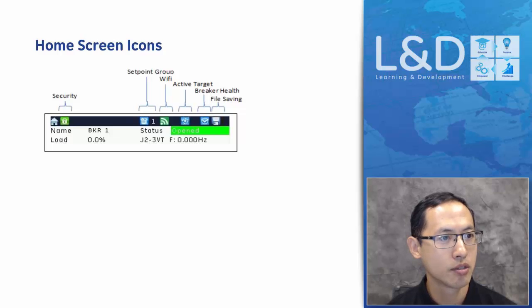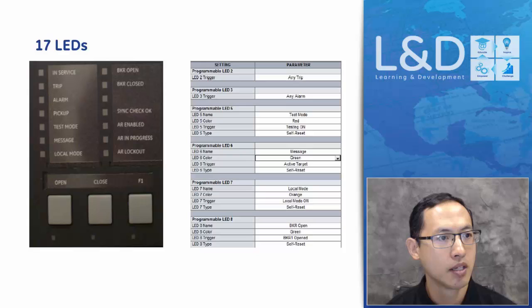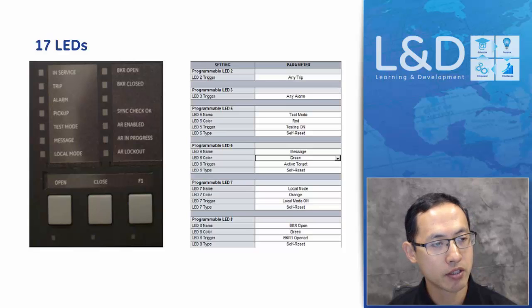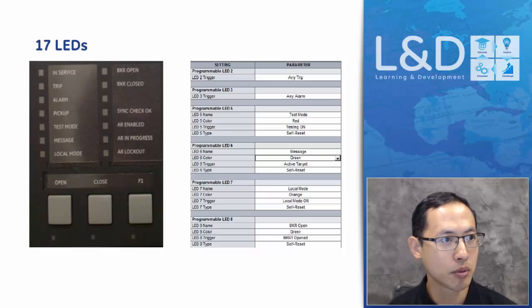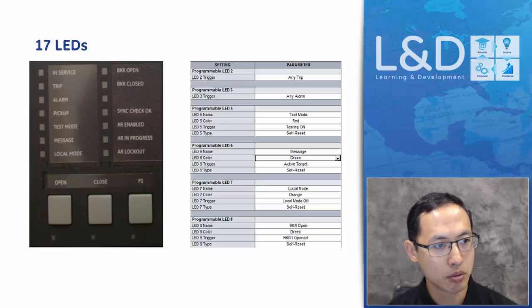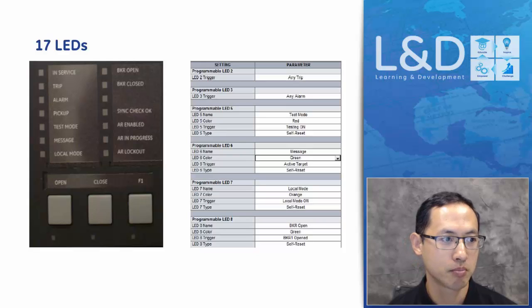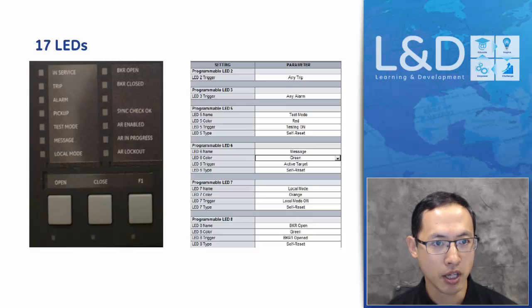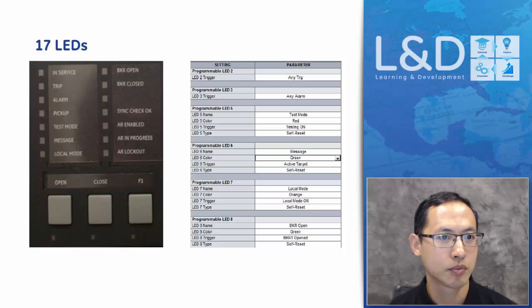We can also see the circuit breaker status, open or closed, and we can see the load current and the measured VT frequency. So for the programmable LEDs, there are 14 LEDs on the top. 2 of them are not programmable, that's in service and pickup. So there are 12 programmable on the top and 3 programmable at the bottom, so totally 15 programmable LEDs. And this can be easily programmed either from the front panel or with the NVISTA software. Each one can be programmed as green, yellow, and red, or green, orange, and red.